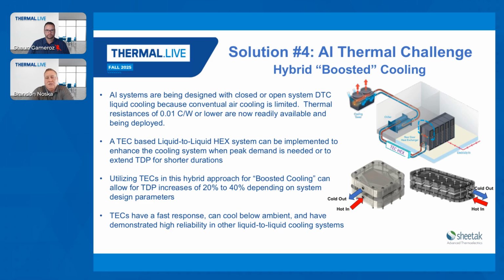Another way of looking at TECs in AI cooling systems: with direct-to-chip liquid cooling and existing cooling loops in data centers, systems are often limited in managing the peak power of the chips. So you can design your thermal system to manage the base load thermal requirements, then leverage thermoelectrically cooled liquid-to-liquid systems to handle the peak demand from the AI chips, and also potentially store reservoirs of colder water to push into the system as needed. The TEC's ability to cool below ambient temperatures with fast response times enables it to work alongside existing liquid cooling systems inside the data center.